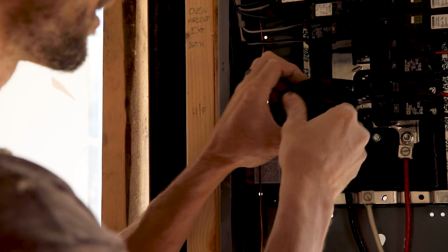So I just wanted to take off one of our 240 volt circuits right here. This one's for the heat pump. And you can see how it's connected to these two metal brackets right here. You see that? So one of those metal brackets goes to our black wire here. The other one goes to our red wire. So you can see how the two are connected inside our breaker. So we've got 120 volts on each one. When they connect here, we get 240 volts going to our heat pump.